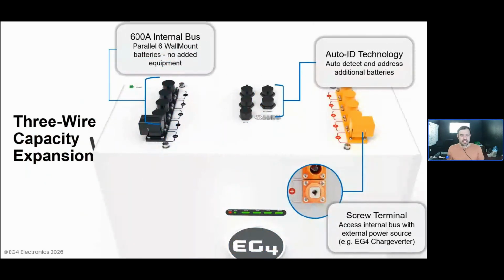We talked a lot about the need to potentially add additional capacity behind inverters, and the EG4 wall mount line of batteries really gives you the easiest means to go ahead and accomplish that task. Essentially, all you need to do to add additional capacity behind an EG4 inverter is run 3 conductors between additional batteries. The 600 amp internal bus of our wall mount battery series can support up to 6 batteries with no additional external bus bars needed on site. That will simply enable you to run a single conductor from the positive, a single conductor from the negative over to the adjacent battery.